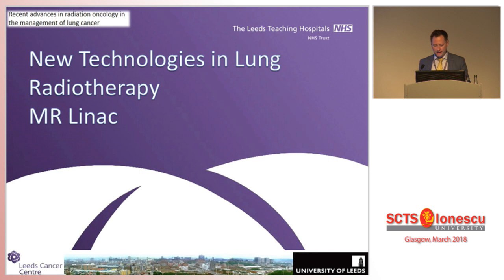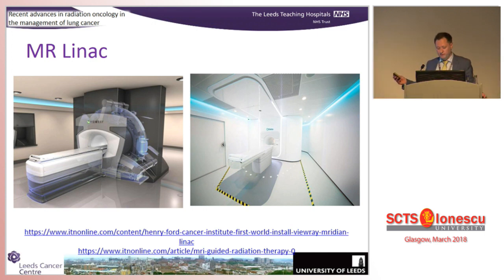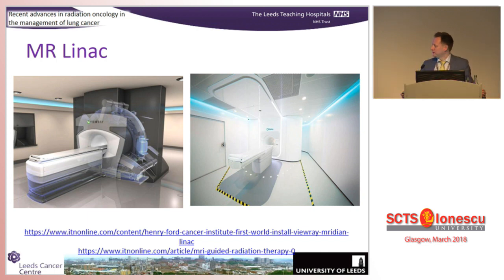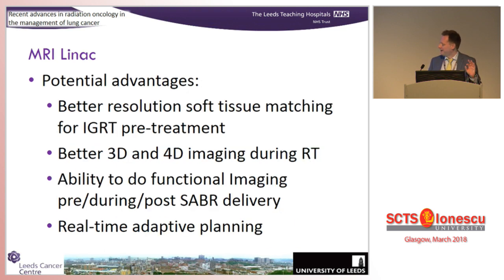One of the ways that's going to drive change is using the MR-LINAC. We now have two MR-LINAC systems: the ViewRay system, which is commercially available - initially a cobalt-based system, but now an MRI-based system - and the Elekta system, which is not commercially available yet but should have FDA approval this year. Why would you want to combine an MRI with a LINAC? It's very technically demanding - a magnet is not very good with radiation beams, it can bend and affect those beams. Very complex physics problems. Two versions are available but not in routine use in the UK.